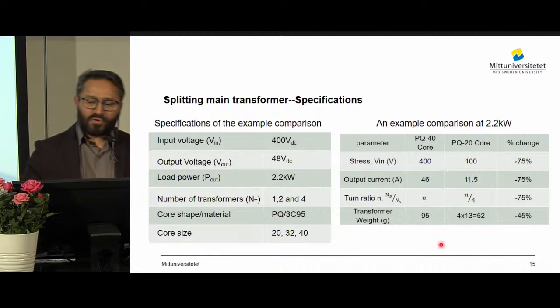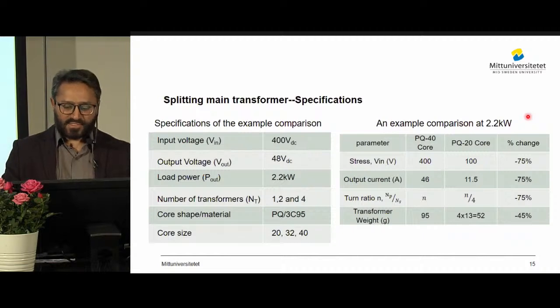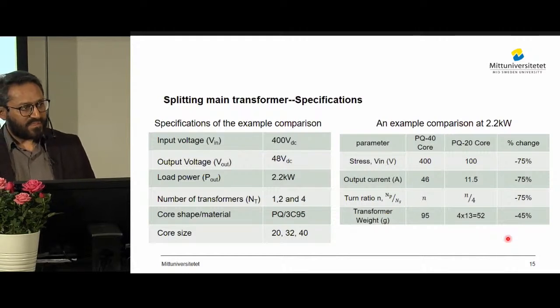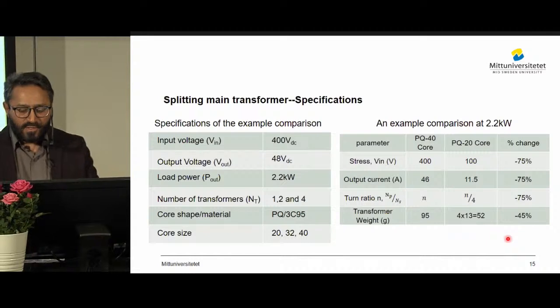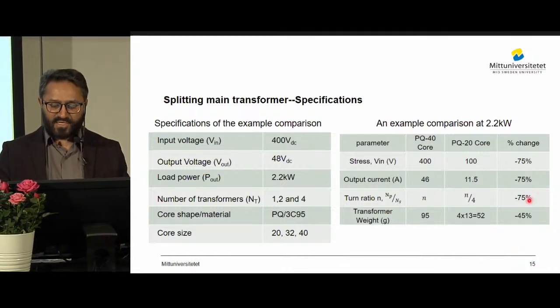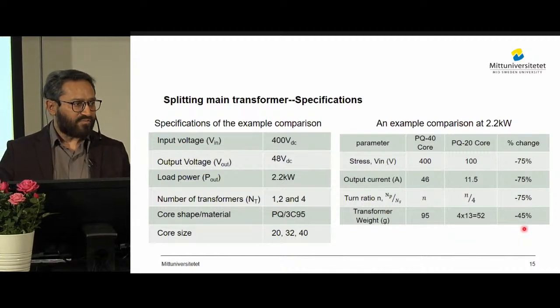So, in comparison, at load power of 2.2 kilowatt, the voltage stress on each transformer in the proposed concept is 75% less as compared to the traditional approach. Similarly, the current stress on secondary elements such as windings, rectifiers and filtering elements will also be less in the proposed design, which cuts the required power ratings of these elements and ultimately reduces the cost. The smaller amount of copper significantly reduces the overall copper losses. Splitting the transformer into 4 cuts the overall transformer weight contribution by 45%.